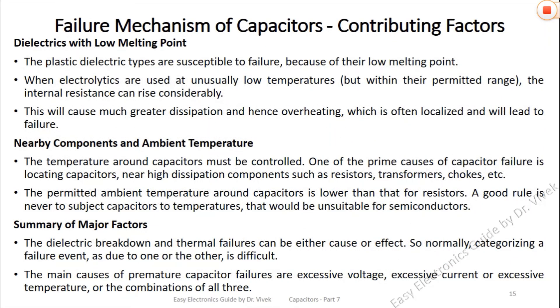Next is the low melting point of dielectric — the plastic dielectric types are susceptible to failure because of their low melting point. Another factor is the ambient temperature. The temperature around the capacitors must be controlled. One of the prime causes of capacitor failure is locating capacitors near high dissipation components such as resistors, transformers, chokes, etc.